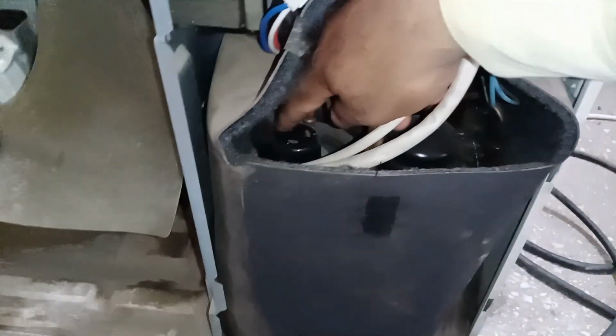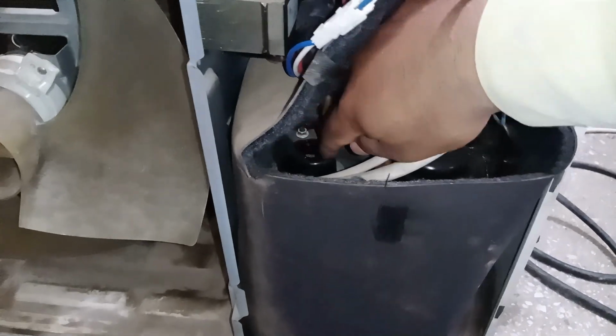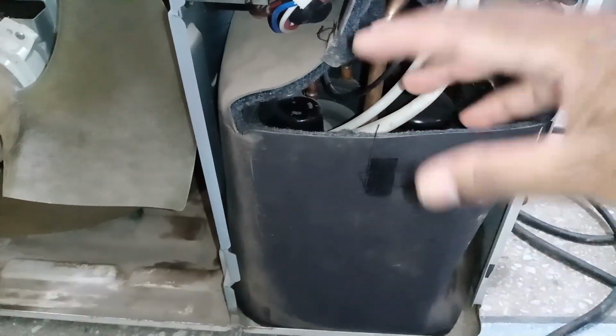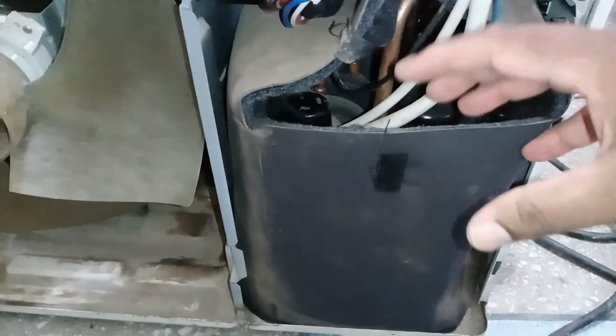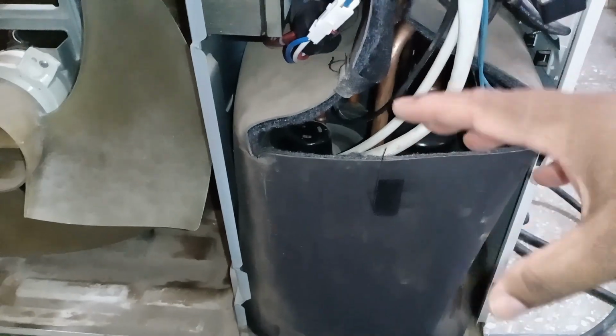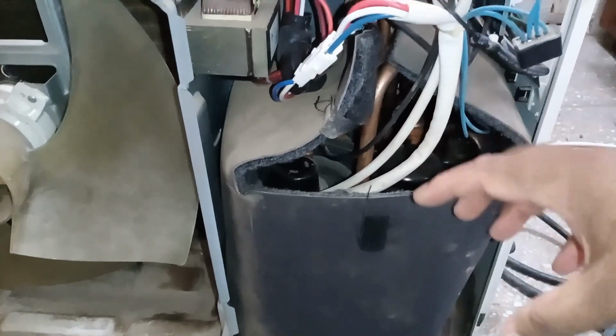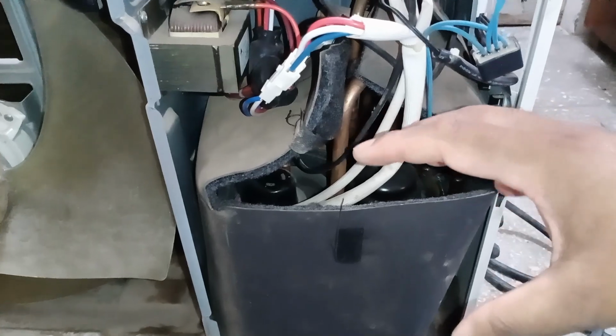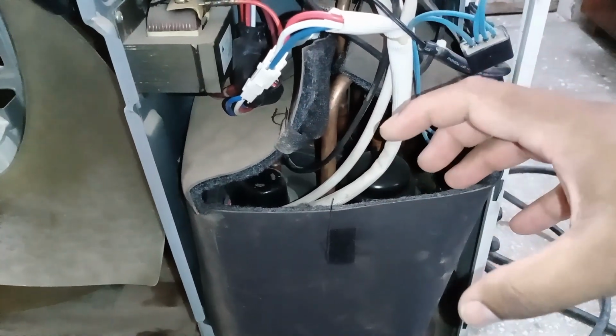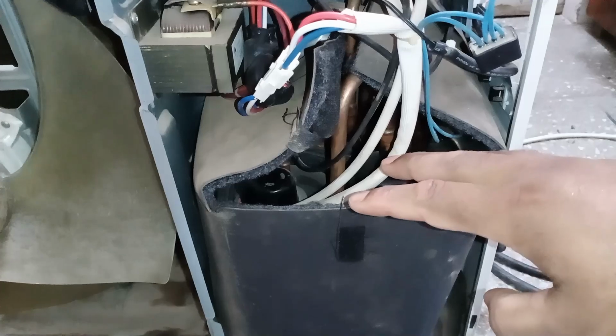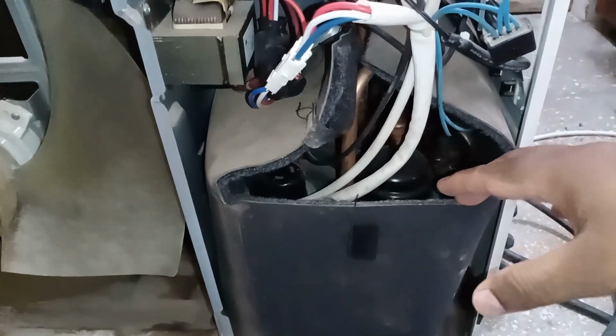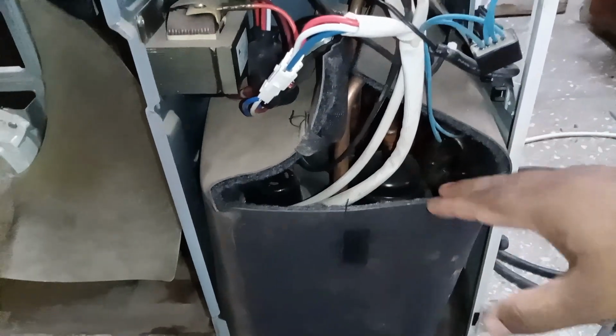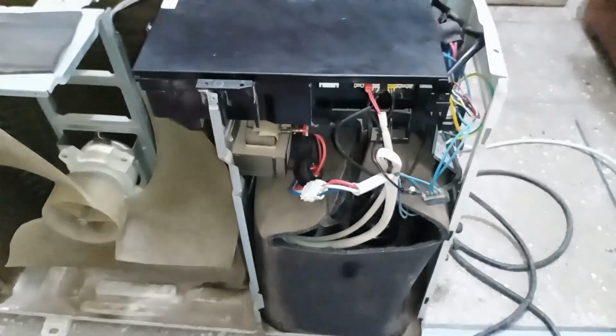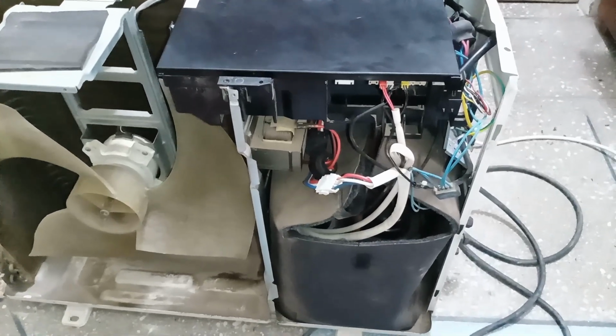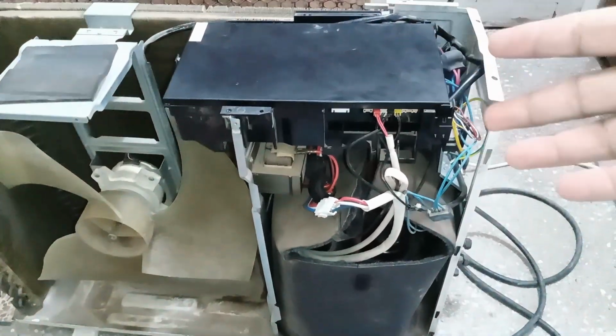Sometimes, the compressor terminals get extremely hot due to overheating or poor contact. If a terminal breaks off or burns out, the compressor will fail to run, and the unit will display error 19. A shorted compressor can also cause this error. If the compressor is jammed, mechanically stuck, it will not start, and the system will register error 19. This happens when the internal parts of the compressor seize up, preventing proper rotation. This system is quite efficient in detecting faults. If you identify and fix these possible issues, the unit will return to working condition.